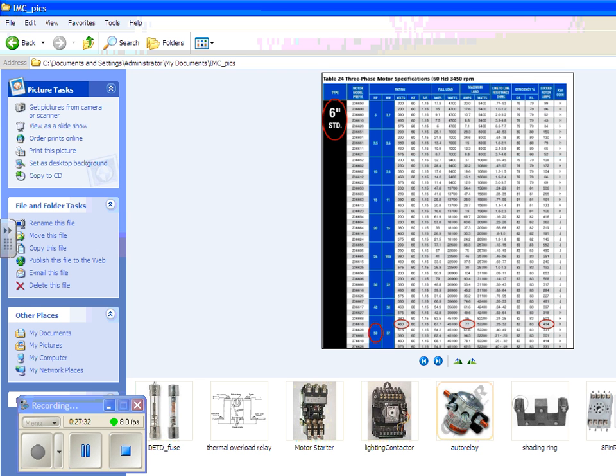And you'll notice in NEMA there's a 1P. What is a 1P? It's for a single phase. And why is there a 1P? Because it's single phase only, and it's a little more than 3 horsepower. It'll go up to 5 horsepower in single phase 120.